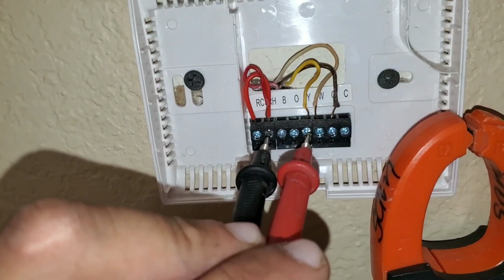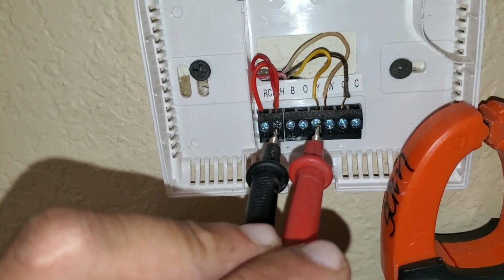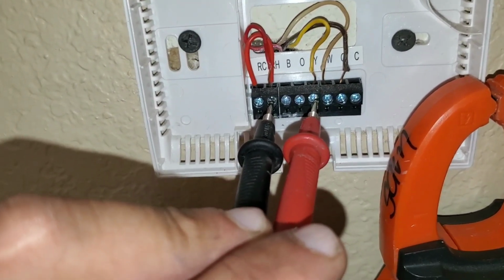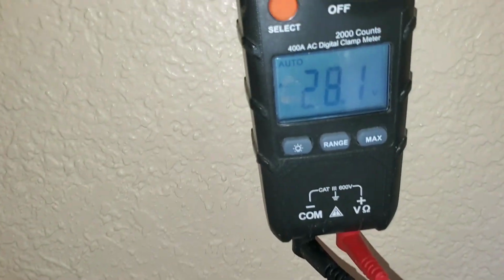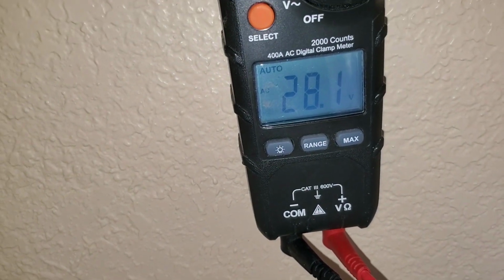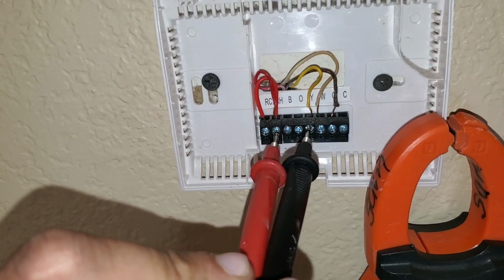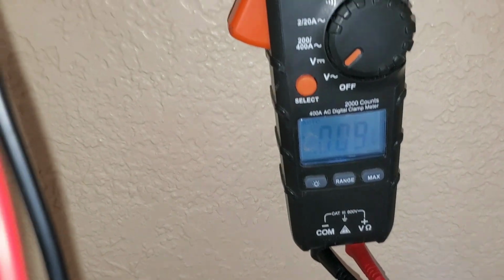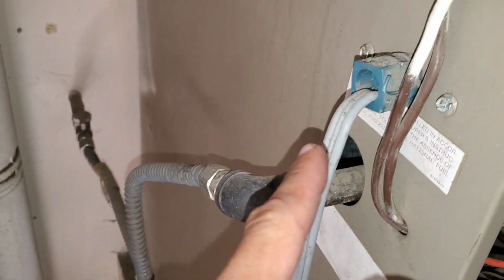I have one of my leads from a multimeter on the R terminal. Here I have it on the Y terminal, and you can see that I now have 24 volts. If you reset the breaker and you still do not have voltage, you'll want to check the 120 volt supply that is coming from your return.